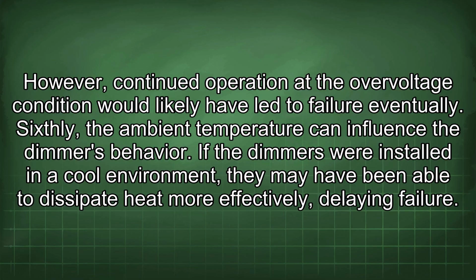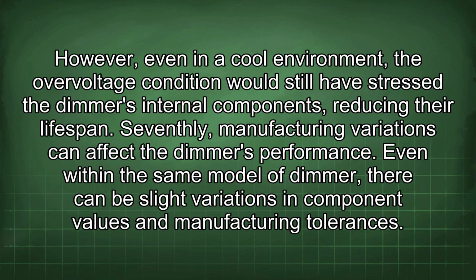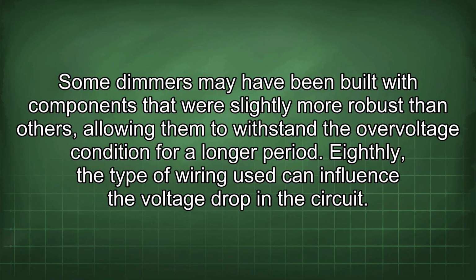Sixthly, the ambient temperature can influence the dimmer's behavior. If the dimmers were installed in a cool environment, they may have been able to dissipate heat more effectively, delaying failure. However, even in a cool environment, the overvoltage condition would still have stressed the dimmer's internal components, reducing their lifespan. Seventhly, manufacturing variations can affect the dimmer's performance. Even within the same model of dimmer, there can be slight variations in component values and manufacturing tolerances. Some dimmers may have been built with components that were slightly more robust than others, allowing them to withstand the overvoltage condition for a longer period.